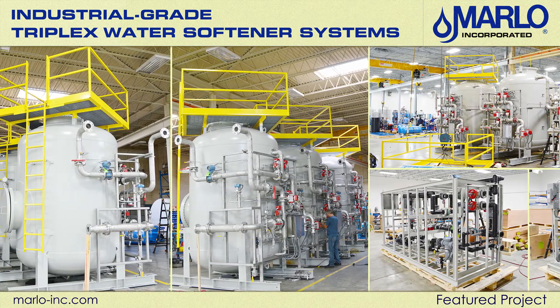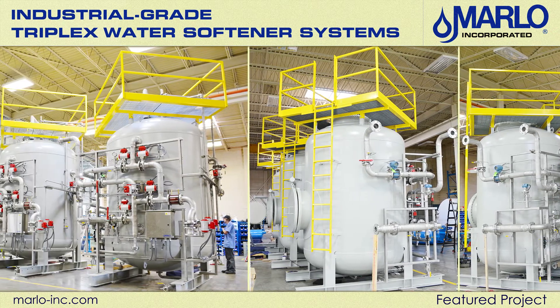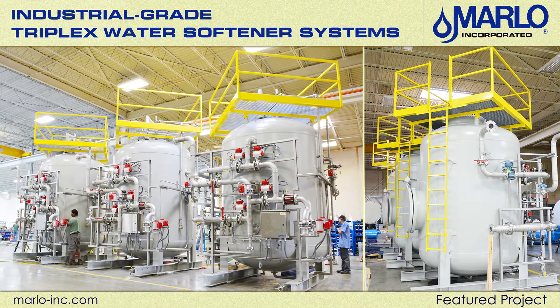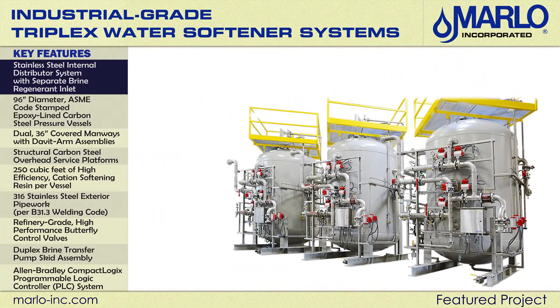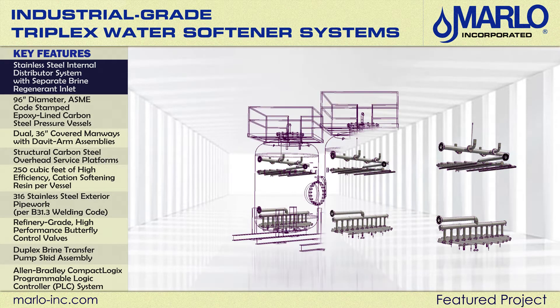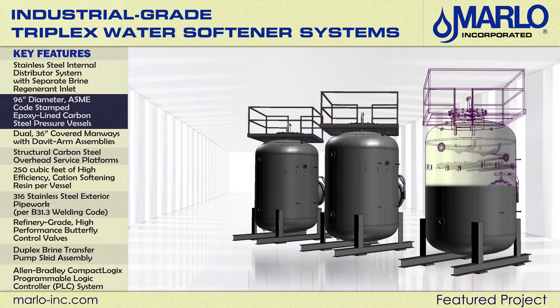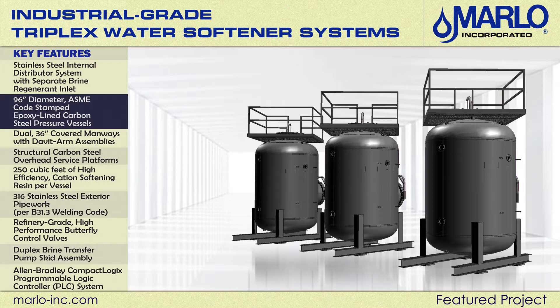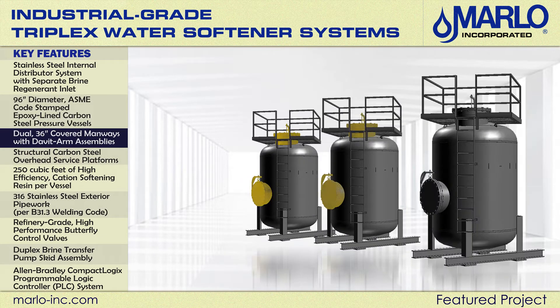The total system capacity is 500 gallons per minute with two vessels online and one vessel in regeneration or standby mode. Key features include a stainless steel internal distributor system with separate brine regenerant inlet, 96-inch diameter, ASME code stamped, epoxy lined carbon steel pressure vessels with a working pressure of 175 PSIG. Dual 36-inch covered manways with davit arm assemblies.